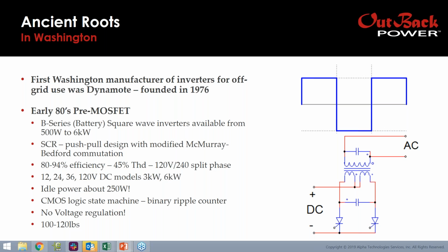They were available in a wide range of battery voltages, because those were the common voltages of the day: 12, 24, 36, and 120 volts DC. The idle power of these units, because of the way the switches switched and took many microseconds to switch, consumed about 250 to 500 watts. All of the logic used to drive them was CMOS logic, discrete and not very flexible, usually using ripple counters of some sort. There was no voltage regulation, so the output voltage was directly a response to the battery voltage. They were also quite heavy, on the order of 100 to 120 pounds for a 4 kilowatt inverter.